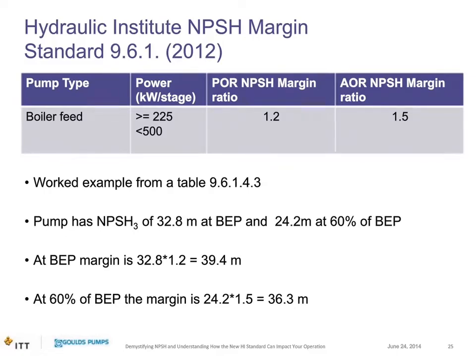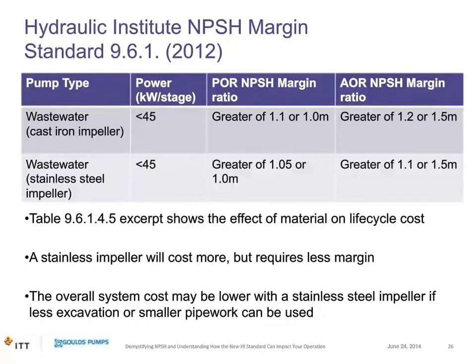Another example: a boiler feed pump with 225 to less than 500 kW per stage. The preferred operating range margin is simply 1.2 — no alternative option given; it is 20% more. The allowable operating range margin is 1.5. With NPSH-3 of 32.8 meters at BEP and 24.2 meters at 60% BEP: at BEP (preferred range), required NPSHA is 32.8 × 1.2 = 39.4 meters. At 60% BEP (outside preferred range, in allowable range), required NPSHA is 24.2 × 1.5 = 36 meters.